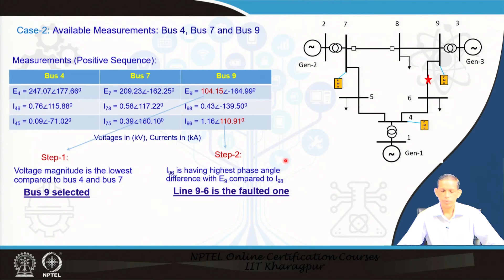In another case, the fault is created between 9 and 6 and the measurements are these. In this set of positive sequence voltages and currents, the minimum voltage comes out to 104, so bus 9 is selected. 2 lines are there, 9 8 and 9 6. The angle between this voltage and this current happens to be significantly high, so the 9 6 line is selected. That is the correct value. So, in both examples we see that from the PMU data, if available, we can find the faulted line correctly, and this faulted line can be useful for further information processing.